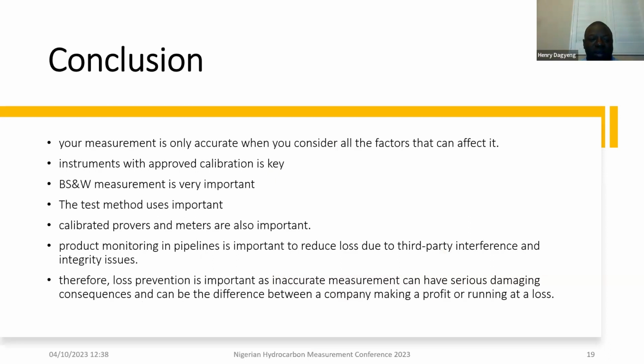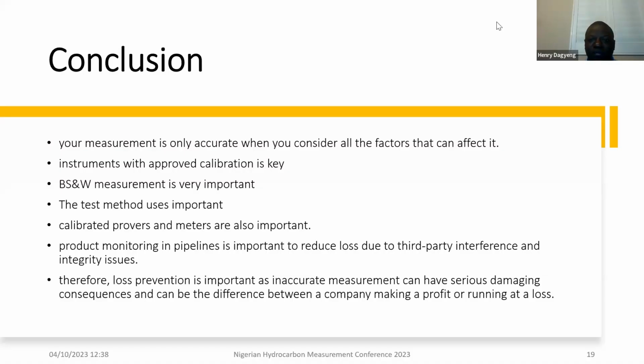In conclusion, your measurement system is only accurate when you consider all the factors that can affect it. Your instruments must have current calibration, and calibration is key, because as simple as it seems, if you have a temperature transmitter that reads wrongly, maybe 3 or 4 degrees difference, that can be huge when the volume is large.